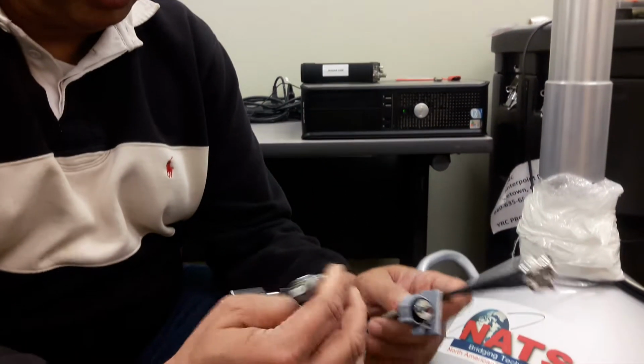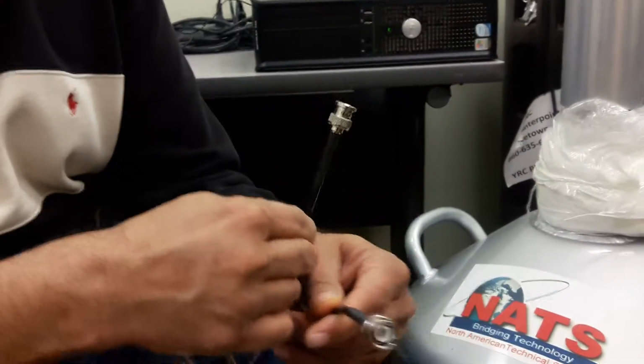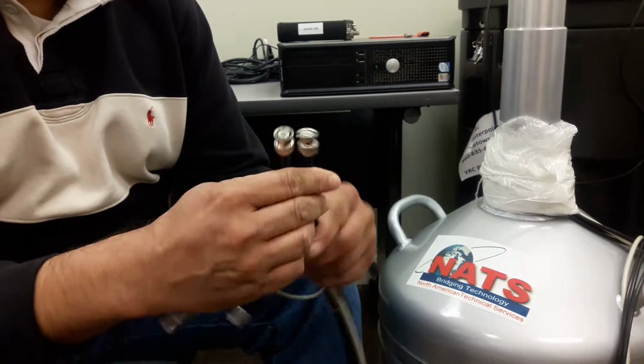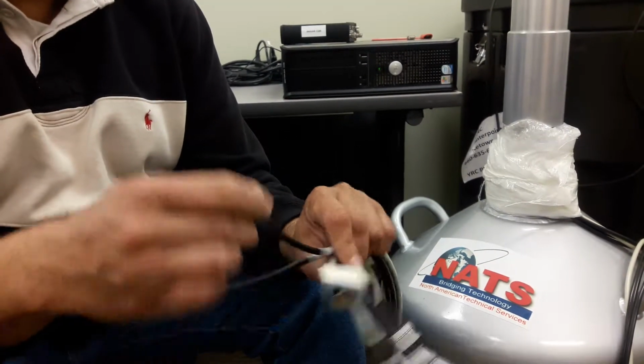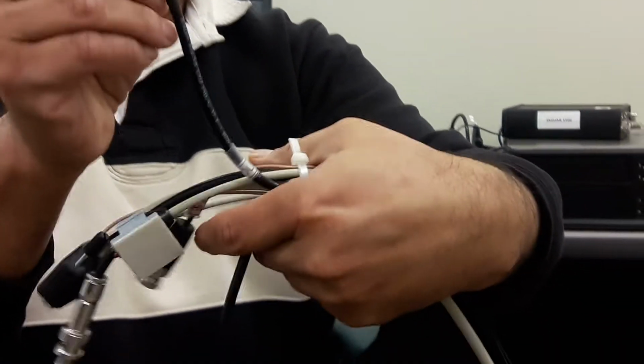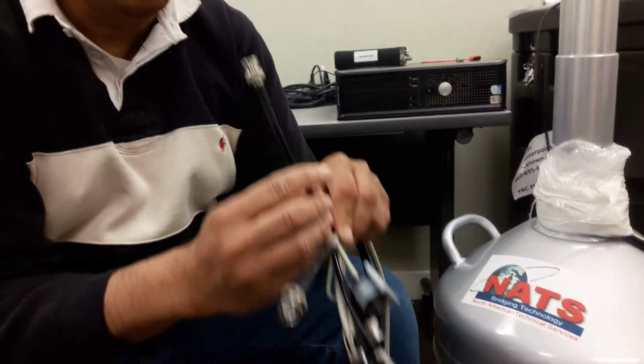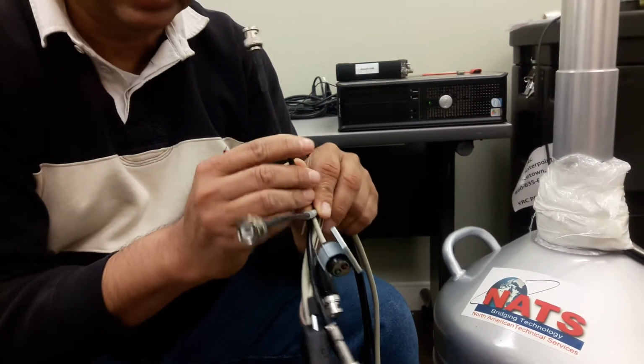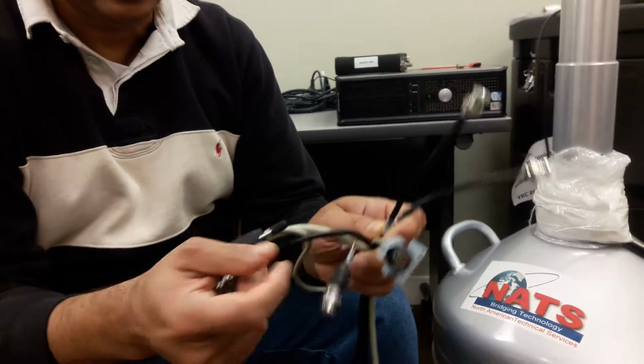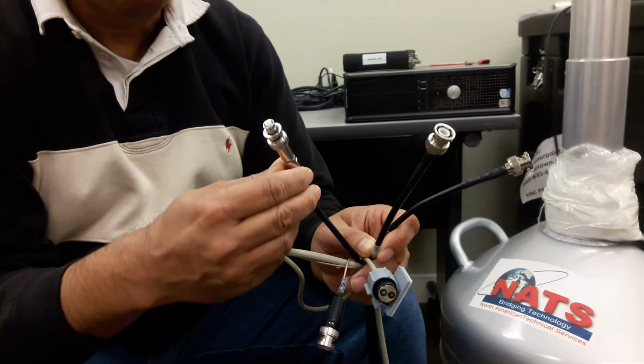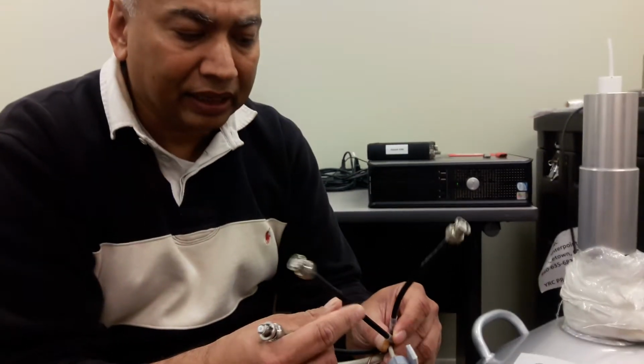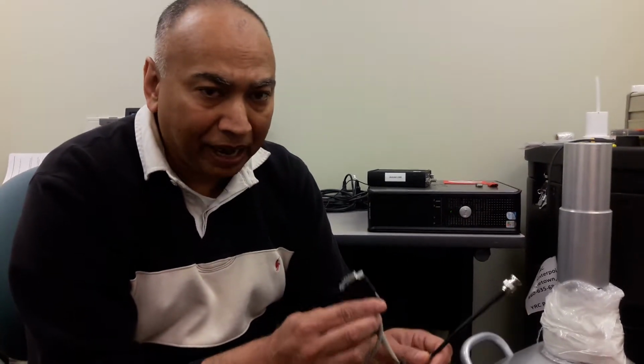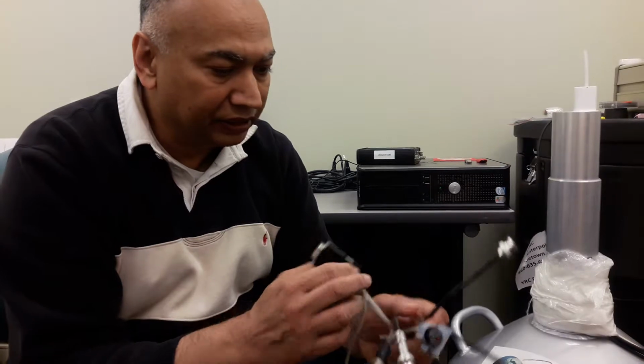In addition to that, you are going to see a number of other connectors in here. There is a high voltage, and another important connector in here is called out. Out is really taking the data out of the system. It's a standard BNC, not to be confused with a test connector. A test connector is used for oscilloscopes and different types of other devices. Most of the time during operations, we are going to use the SHV to provide the high voltage to the detector, and the data out connector, which is a BNC connector like this, and then the preamp power, which provides preamplifier power to the detector.